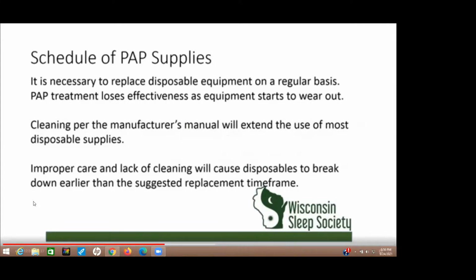In order for CPAP to work effectively, it's necessary to replace the disposable supplies on a regular basis. The cushions, the head straps, the hose, the humidifier chamber, all that stuff. The PAP treatment loses its effectiveness as the equipment isn't new anymore and starts to break down and wear out. Cleaning per the manufacturer's manual will extend the use of most disposable supplies, and improper care and lack of cleaning will cause the disposables to break down and therefore not last the suggested replacement time frame.